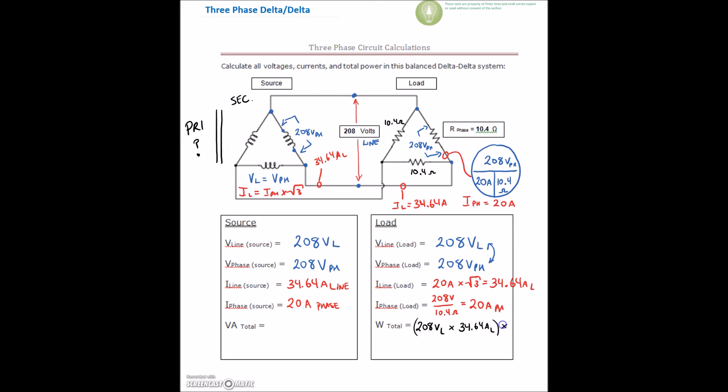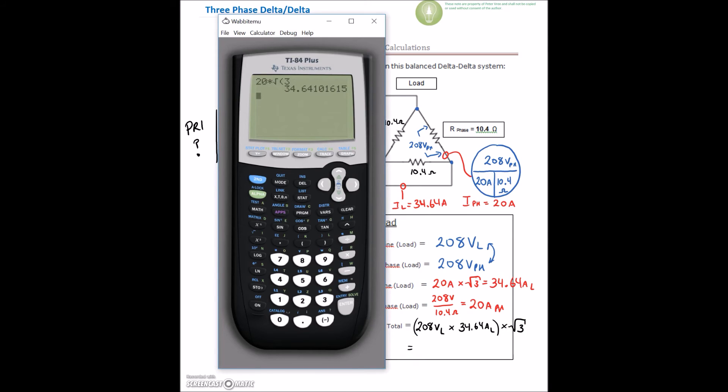So for this guy, I can do 208 volts on the line. My line current is 34.64 amps on the line, and I'm going to multiply those guys by root 3. We've got 208 times 34.64 times the square root of 3. That gives me 12,479.63.